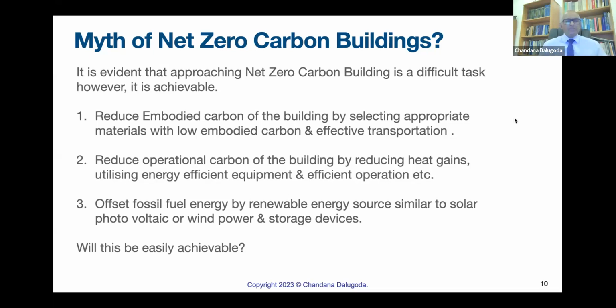Next item, reduce operational carbon of the building by reducing heat gains. As we know, a building consumes energy. If you take a 3-4 story office building, the majority of energy use is for air conditioning systems in this kind of tropical humid climate, probably heating in a cold country. Plus the lights, lifts, plug loads, ventilation and so forth, all consume energy. Now, the air conditioning system usually consumes 50 to 60% of the total energy consumption of a building.